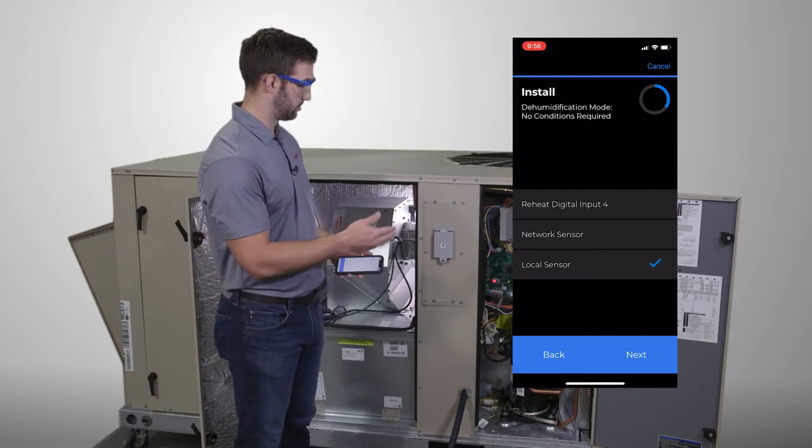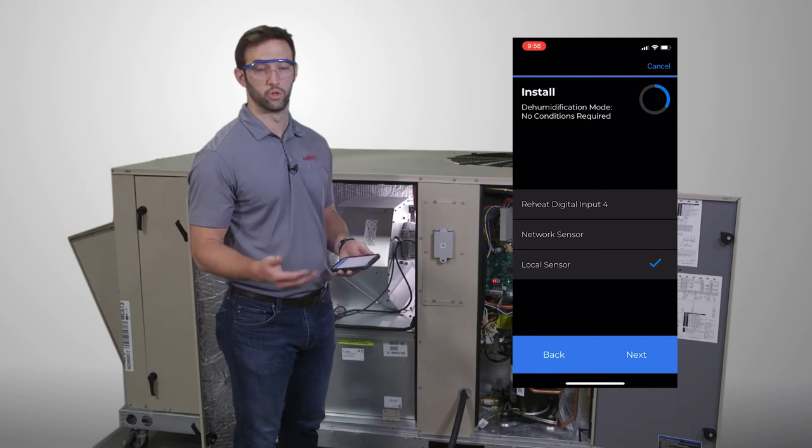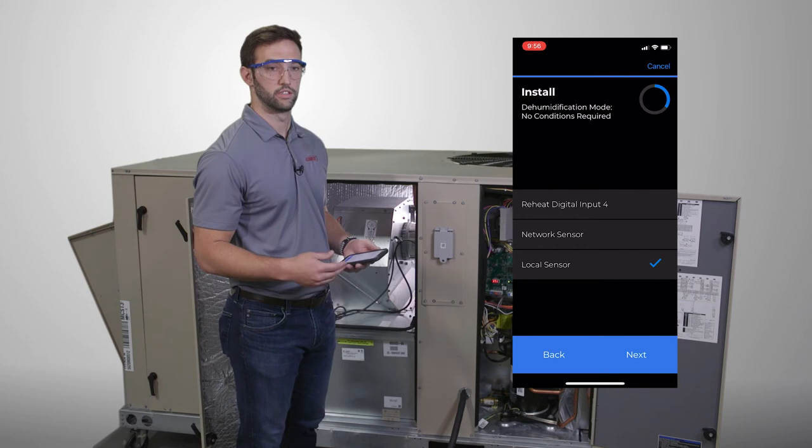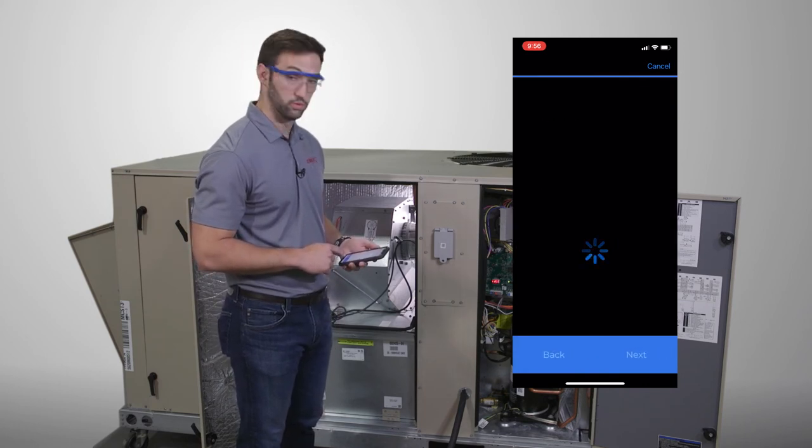So your options are your DI4 for 24 volt controls. You'll have your network sensor or local sensor that can be a 0 to 10 volt or that can be a CS8500, something like that, that provides that value to the core controller.